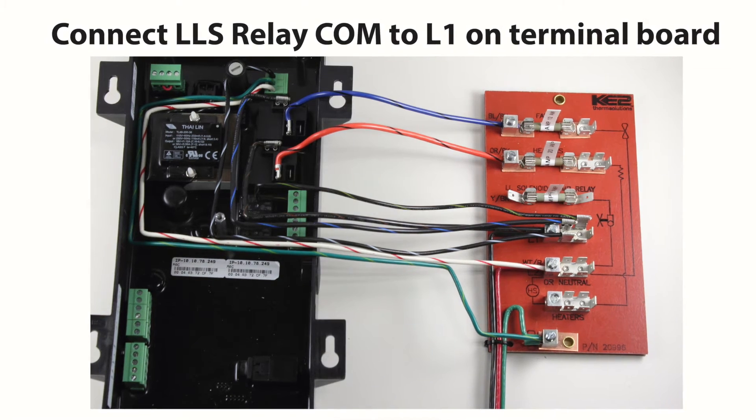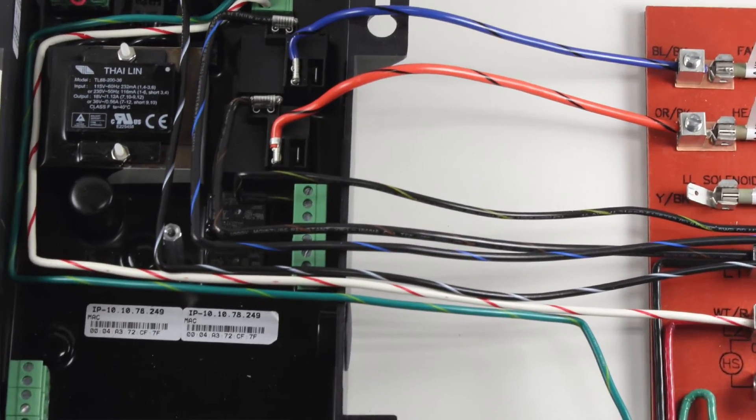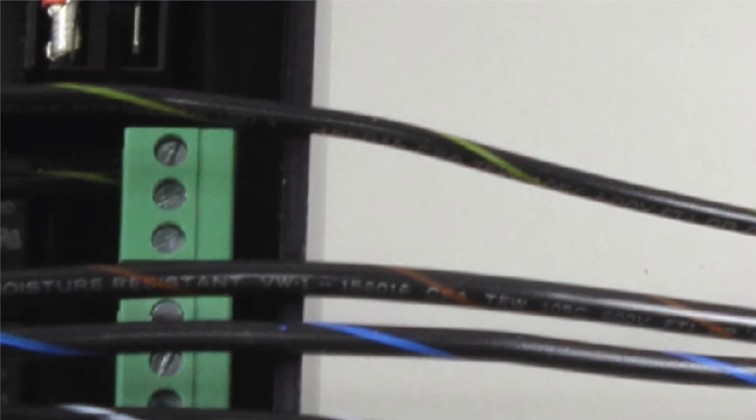Next, the liquid line solenoid relay dry contact needs power provided to the common terminal. Connect line 1 on the terminal board using the black with yellow stripe. Wire to the common on the liquid line solenoid relay as shown.